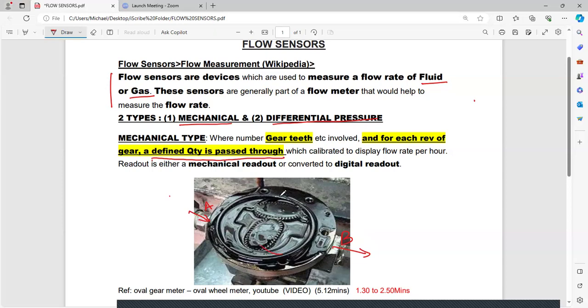How much will depend on how much these particular gears rotate. This is coupled to a readout, whether mechanical or digital. You don't need any power to operate this because there is positive displacement. When pressure acts in this direction with regard to flow, more flow means more pressure acting, less flow means less. Accordingly, these gears turn faster or slower, and you get your readout of flow from point A to point B. A defined quantity of liquid passes through that mechanical flow sensor.